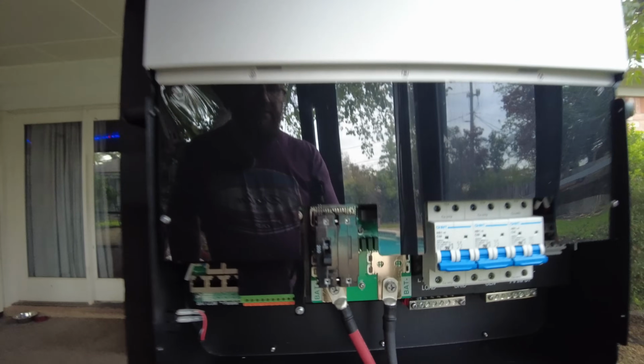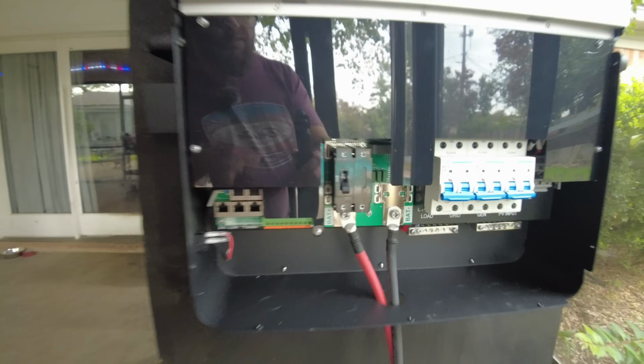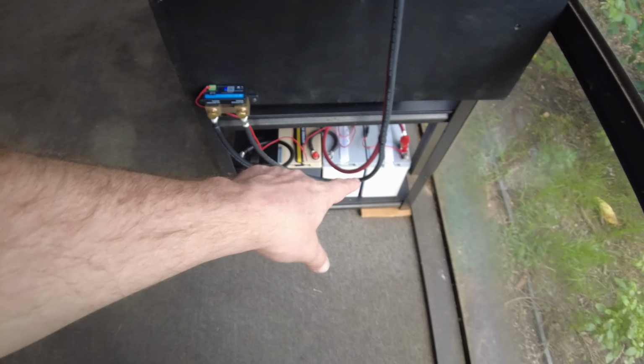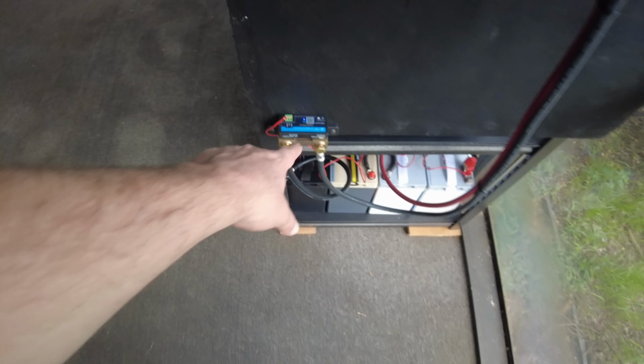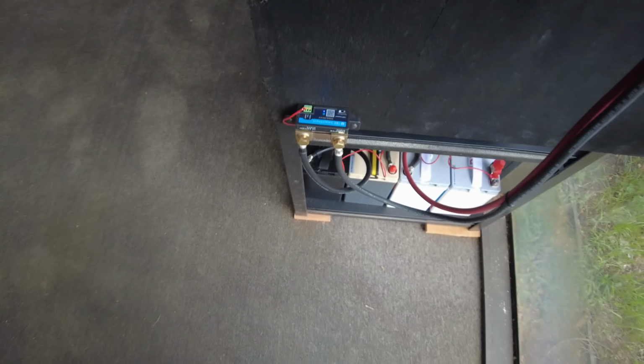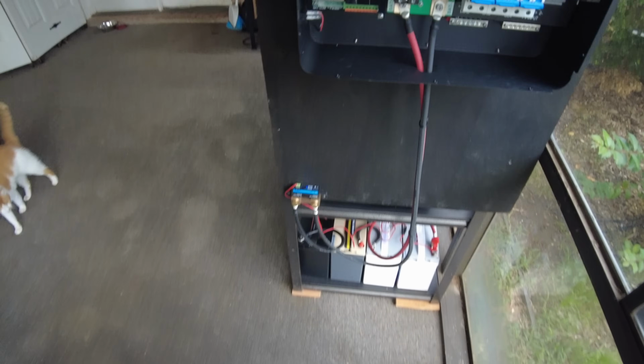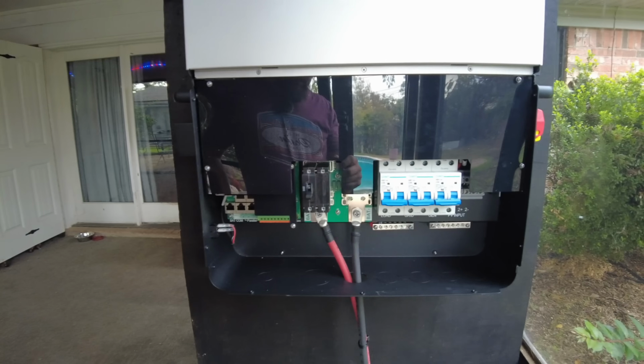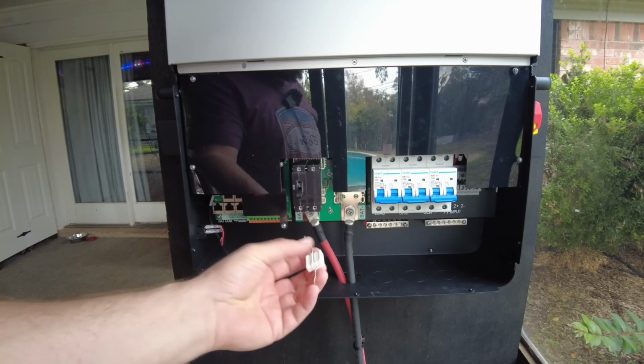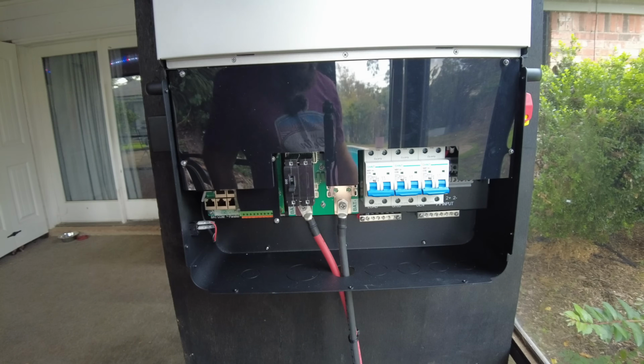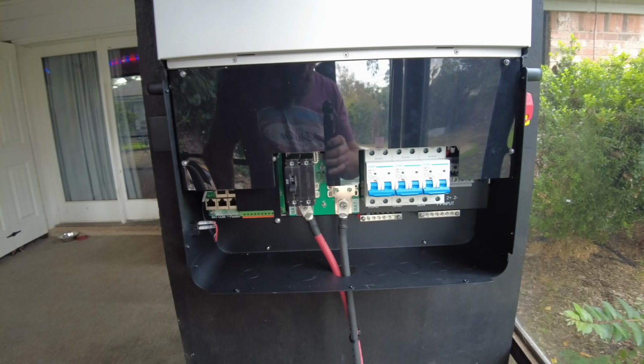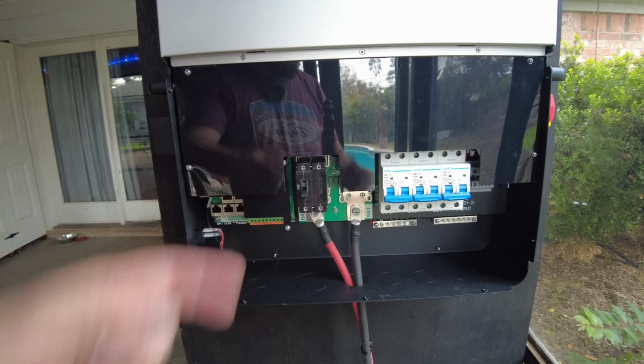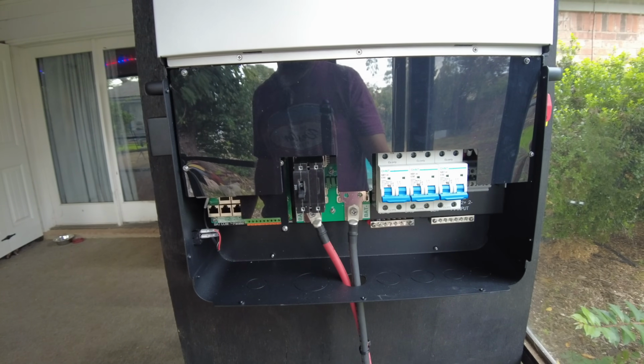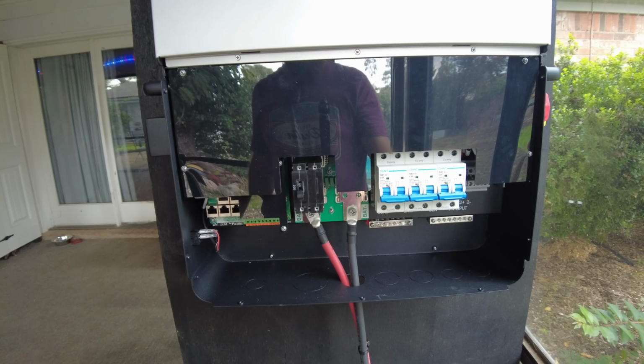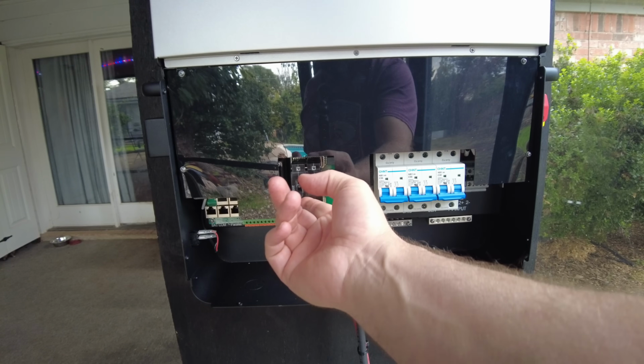All right, guys, so I got the DC wiring all hooked up. And I've got the batteries all ran in series down here. And also got a shunt so we can monitor the power going in and out of the batteries. And I did go ahead and pre-charge with these resistors for about 10 seconds. I wasn't quite sure if that was necessary on this unit. Some of these are coming with pre-charge resistors built in. Also, some of the batteries do, but these batteries don't. Let's go ahead and flip this back on.